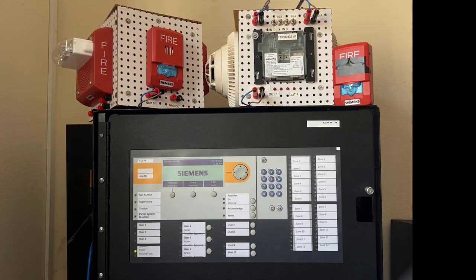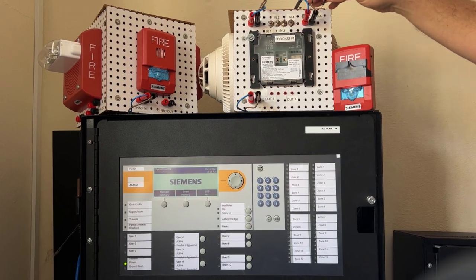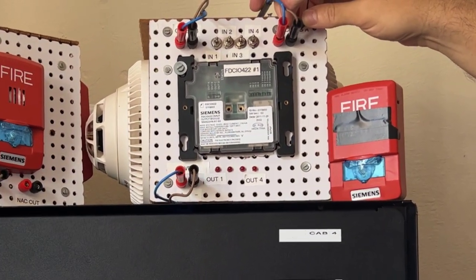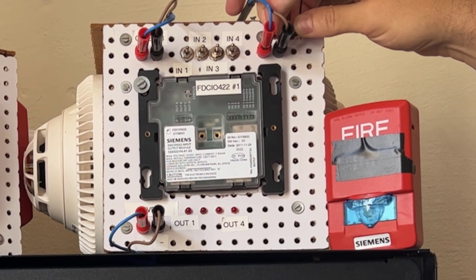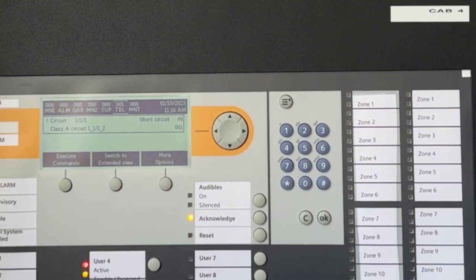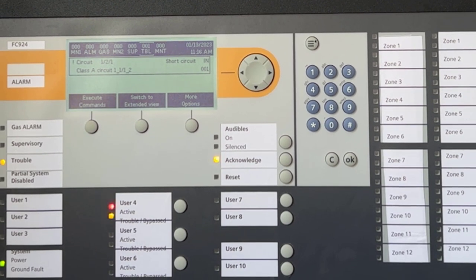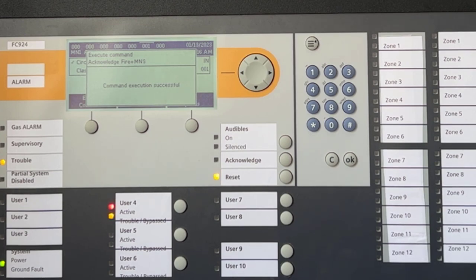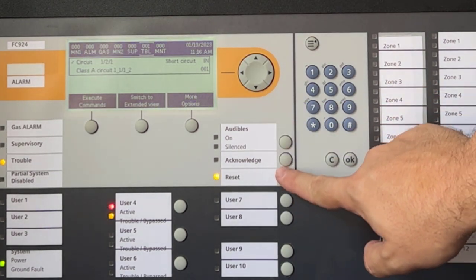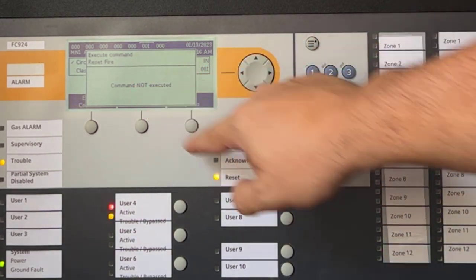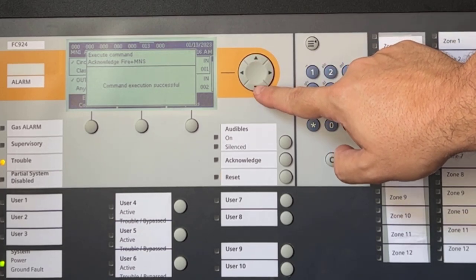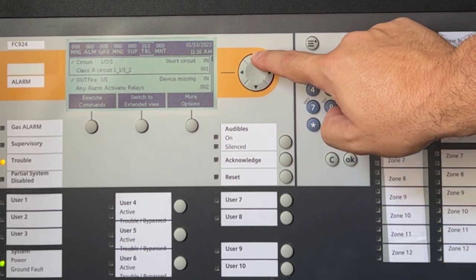Next, I created a short circuit condition on the loop and I have no isolators on my circuit. This means that the entire circuit will shut itself off for self-protection. And in addition to the short circuit event, I have all my devices on the loop missing, and a few other trouble events for my audible bases, some relays, etc.